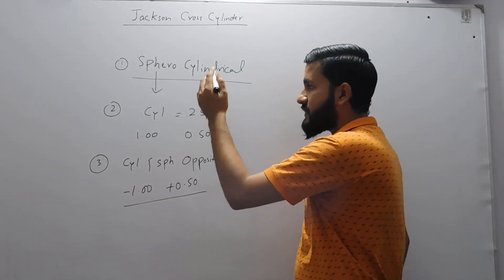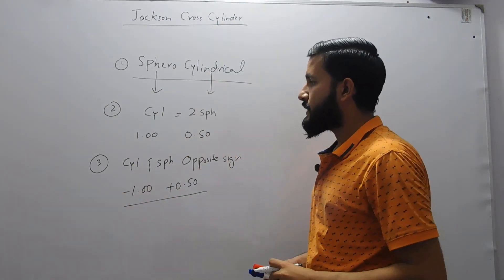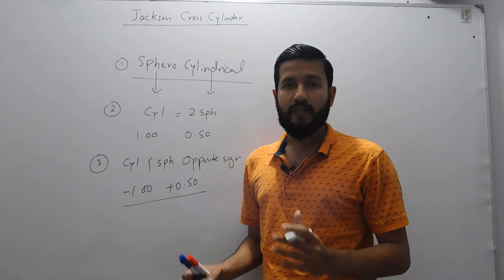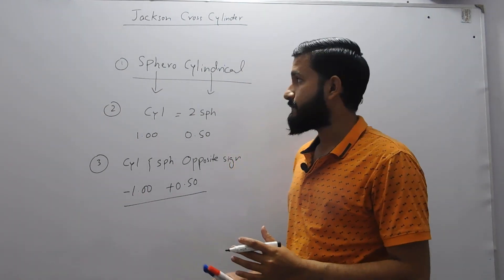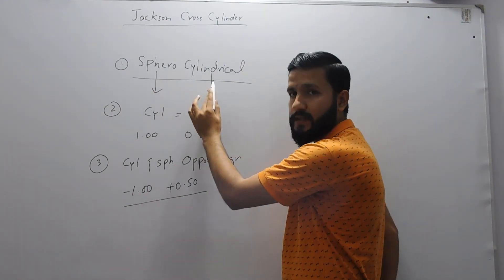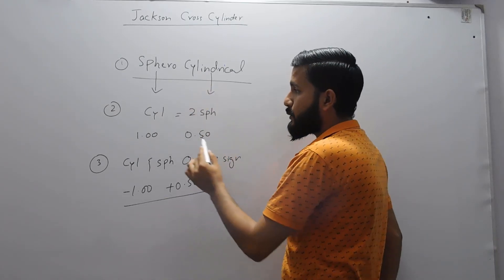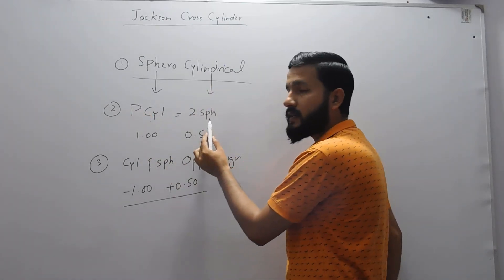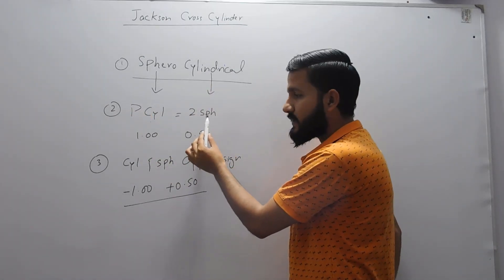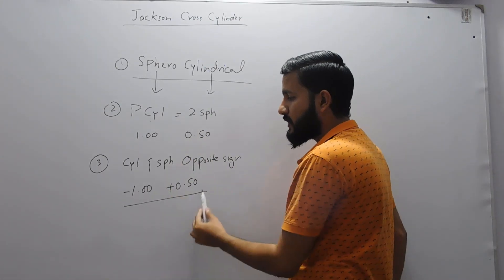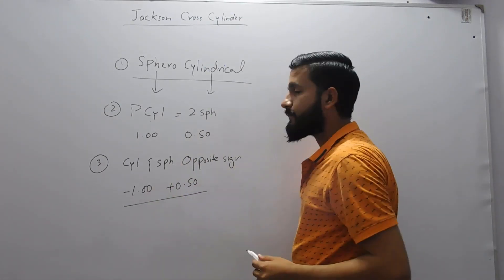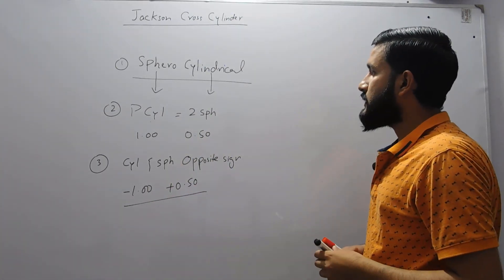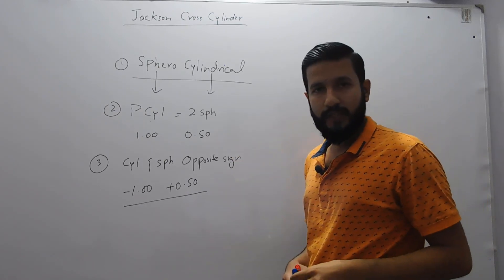If the sphere is plus 0.50 then the cylinder will be minus 1. So these three points complete the definition of Jackson Cross Cylinder: it is a sphero-cylindrical lens in which the power of the cylindrical lens is double that of the spherical lens and is of opposite sign.